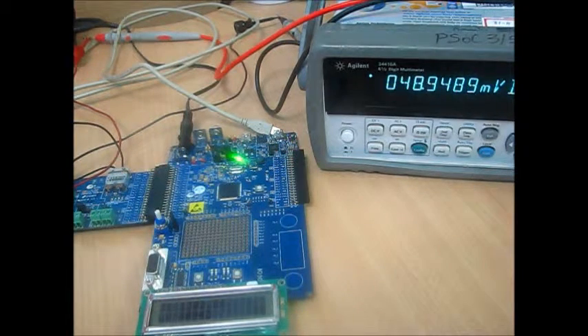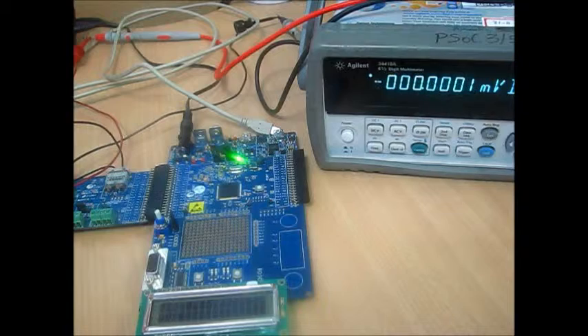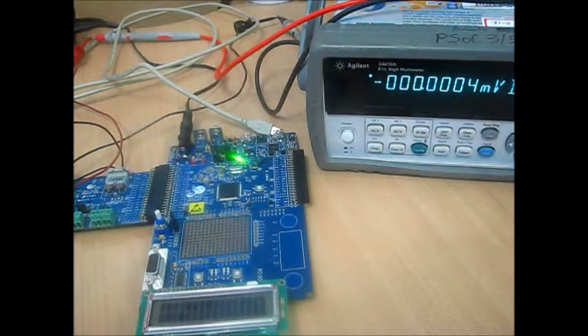There is a small variation in the output flicker on the LCD. That's because the input is not very stable. The same flicker can be observed in the multimeter too. Let's change the input voltage to some other value and check how the reading goes. So I vary the input to a very low value, around 0 volts. Now the multimeter reads 0 volts and my input value is 4 to 5 microvolts. There's a small difference of 4 to 5 microvolts in this reading.